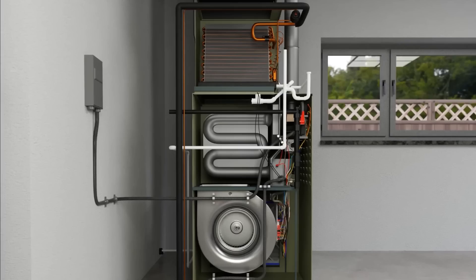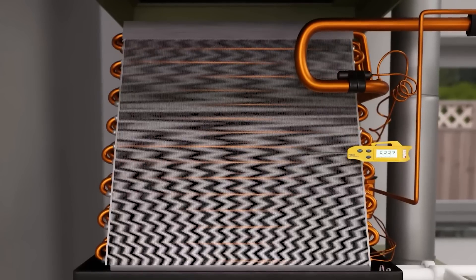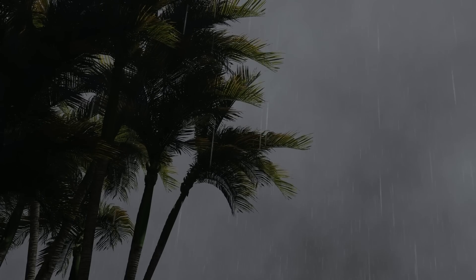Also, things that can reduce indoor relative humidity — make sure the equipment is set up properly. Equipment that runs a long time and has a cold evaporator coil is the best way to control humidity in the space during peak load conditions. But the times that we generally find the worst cases of vent sweating are cases where either the occupant is leaving doors and windows open and letting a lot of moisture come in, or periods when it really isn't that hot — maybe rainy seasons, maybe in the spring, maybe there's hurricanes that come through. In Florida, hurricanes drive a lot of moisture into the buildings, but it's also cool outside, so the equipment doesn't run as much. We want the equipment to run a lot at a low evaporator temperature.